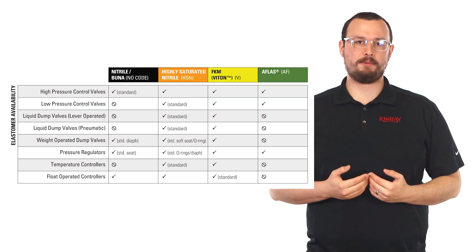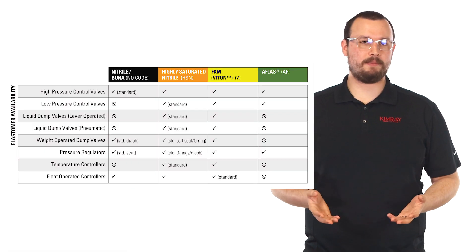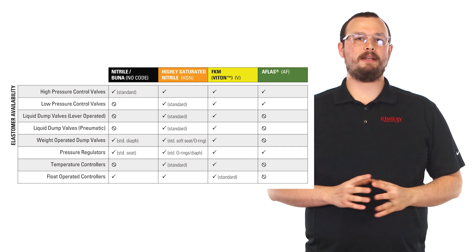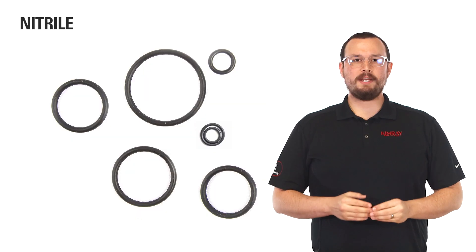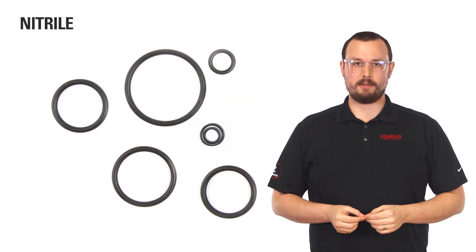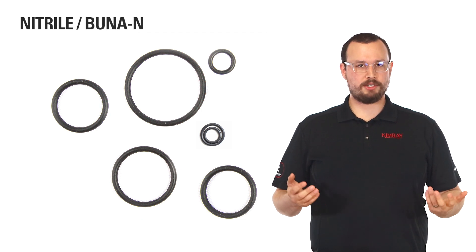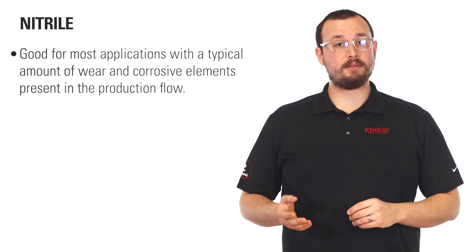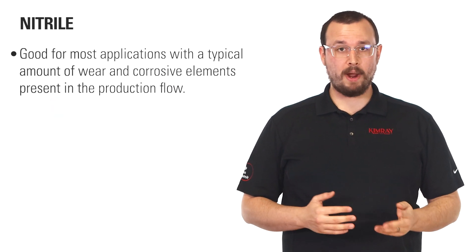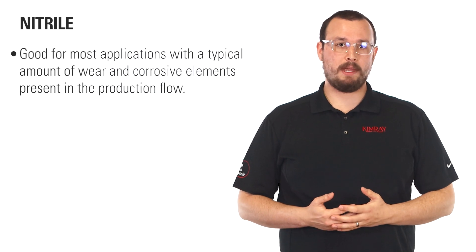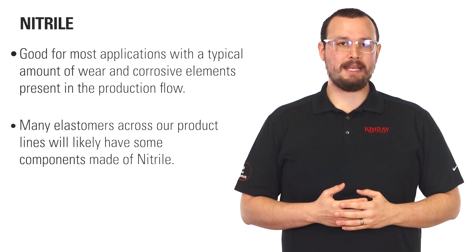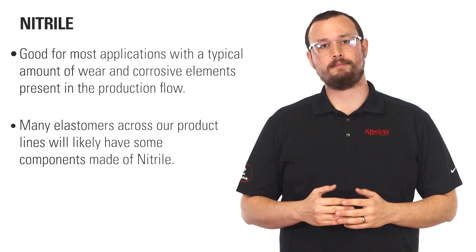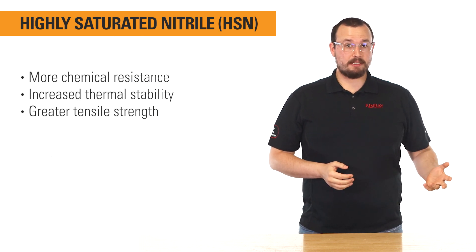Kimray has narrowed down our options to help make the selection easier. There are some components within products that have further options, but these four materials are the primary considerations. Nitrile is a synthetic rubber commonly used in elastomers. It's also known as BUNA-N or just BUNA, which is a common name for all classes of nitrile. It's good for most applications with a typical amount of wear and corrosive elements present in the production flow. No matter which kit or selections you make, many elastomers across our product lines will likely have some components made of nitrile.